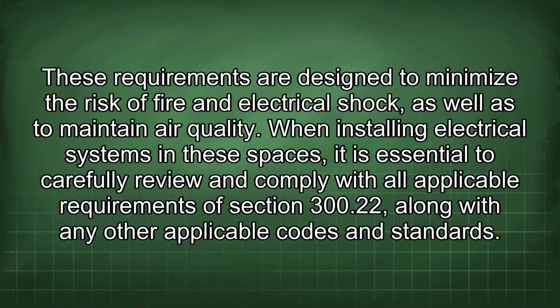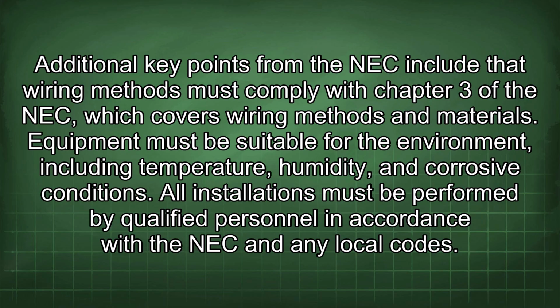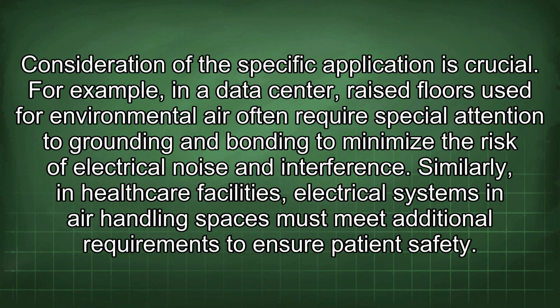When installing electrical systems in these spaces, it is essential to carefully review and comply with all applicable requirements of Section 300.22, along with any other applicable codes and standards. Additional key points from the NEC include that wiring methods must comply with Chapter 3 of the NEC, which covers wiring methods and materials. Equipment must be suitable for the environment, including temperature, humidity, and corrosive conditions. All installations must be performed by qualified personnel in accordance with the NEC and any local codes. Consideration of the specific application is crucial.